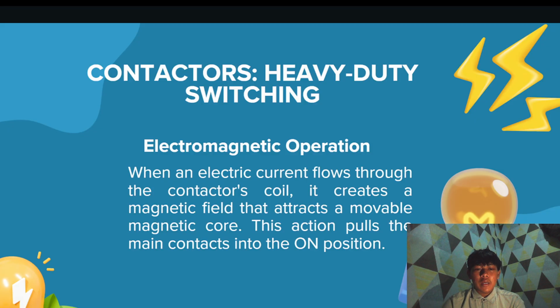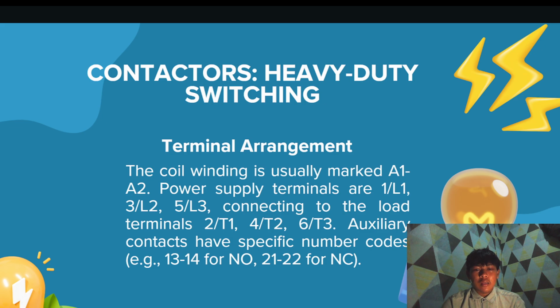Electromagnetic operation. When an electric current flows through the contactor coil, it creates a magnetic field that attracts a movable magnetic core. This action pulls the main contact into the on position. Terminal arrangement. The coil winding is usually marked A1 and A2. Power supply terminals are 1L1, 3L2, 5L3, with connections to the load terminals 2T1, 4T2, 6T3. Auxiliary contacts have specific number codes.